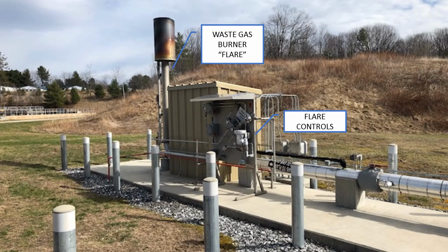The waste gas burner system, which most people refer to as the flare, is put in place for times that we have exceeded our utilization. We're making more gas than we can use or store, or times when our equipment is down and we've exceeded storage capacity. The gas has to have some place to go. The safest place for it to go is to be burnt and sent to the atmosphere.